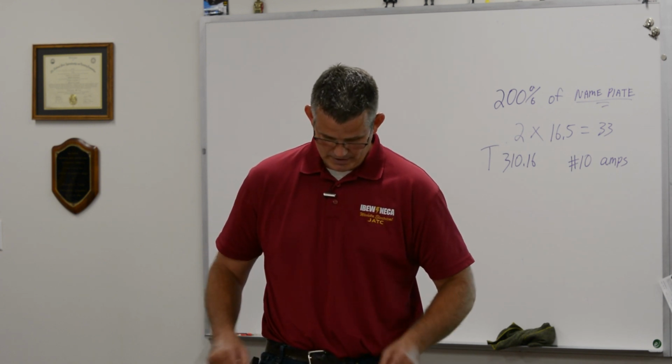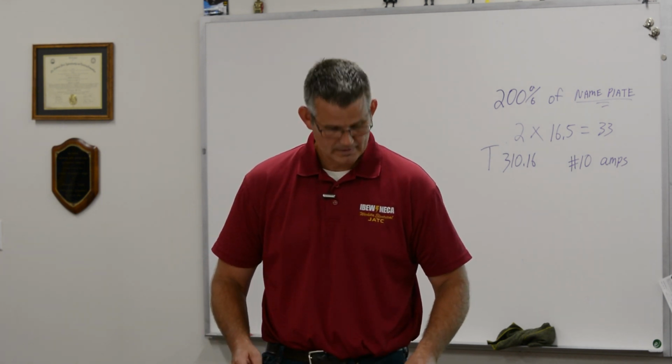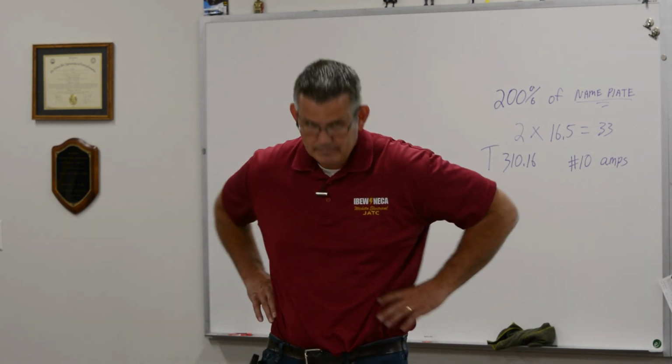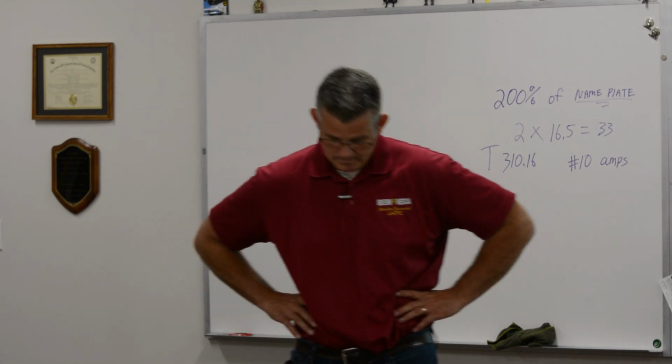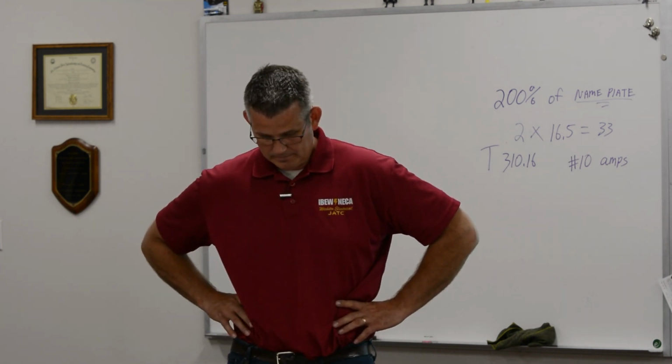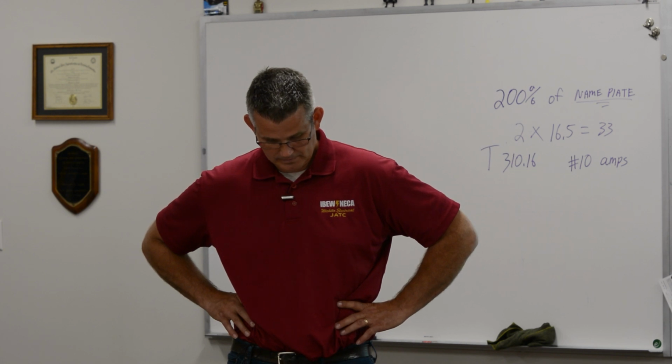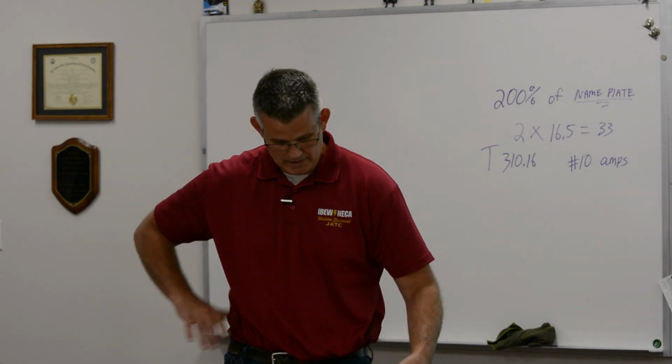Okay, let's look at 240.4(D). Number 7, 10 AWG copper, 30 amps. You guys see that? All right, what's number 12? 20 amps, right? In 310.16 number 12 is a 20 amp wire.